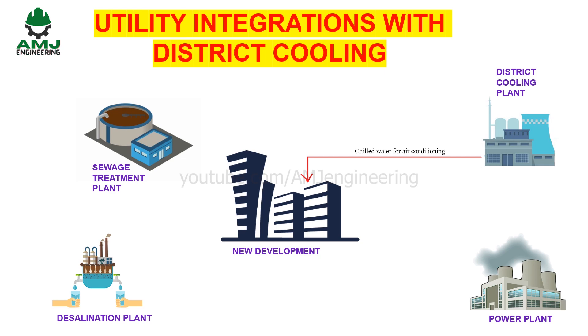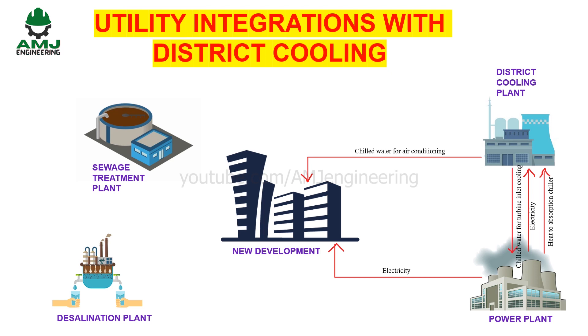There is now widespread recognition of district cooling's ability to cut power demand and energy, thus reducing government investment in power infrastructure as well as power utility operating costs. Due to its higher efficiency compared to other cooling systems, district cooling frees up power capacity to meet other electricity requirements of new developments. Another potential synergy is the use of gas turbine inlet air cooling, which increases power generation when the ambient air temperature is high.